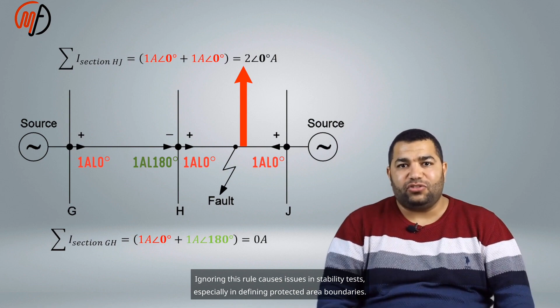If the polarity is incorrect, the relay will consider all incoming currents as outgoing and all outgoing currents as incoming. CT placement determines each protection zone's start and end. This CT monitors all currents in the protected zone, so its placement must be strategic for overlapping protection.